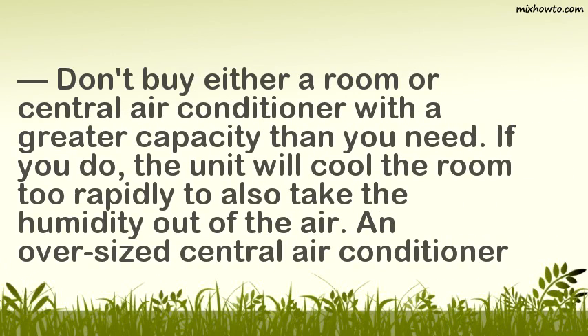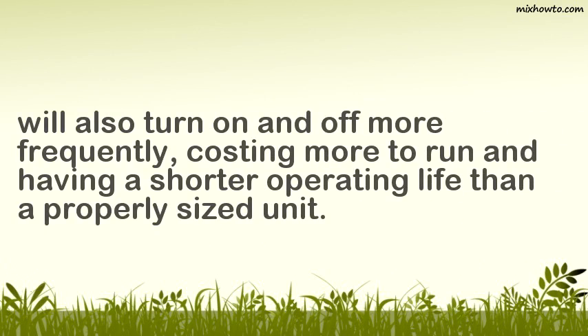Warnings: Don't buy either a room or central air conditioner with a greater capacity than you need. If you do, the unit will cool the room too rapidly to also remove the humidity from the air. An oversized central air conditioner will also turn on and off more frequently, costing more to run and having a shorter operating life than a properly sized unit.